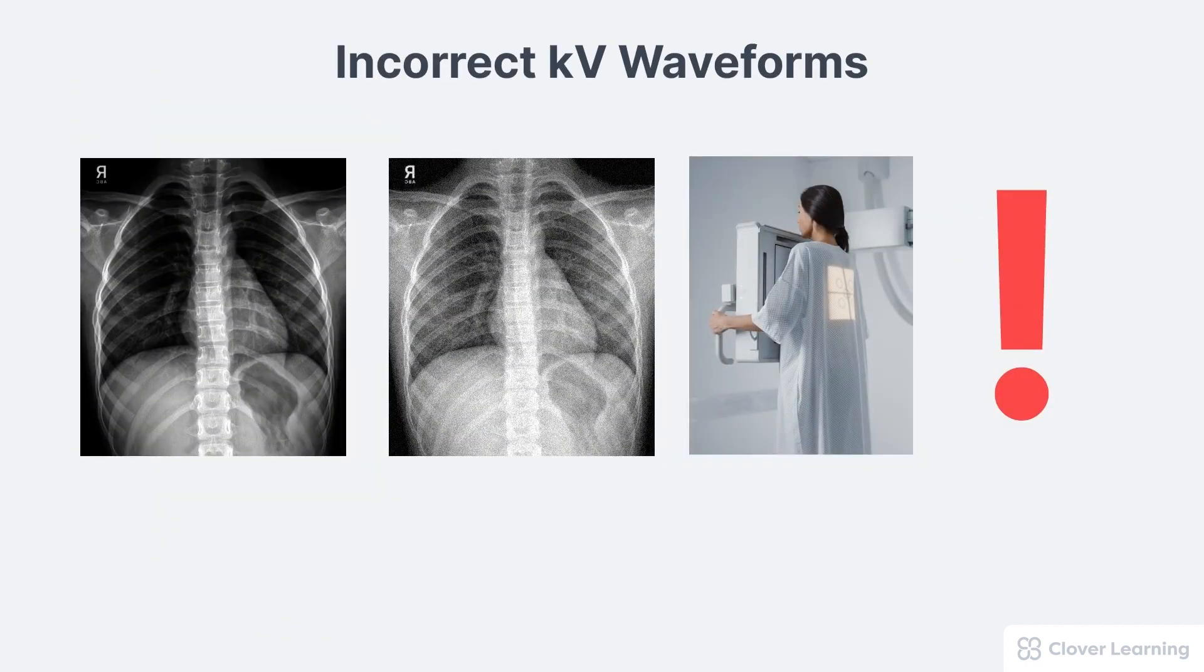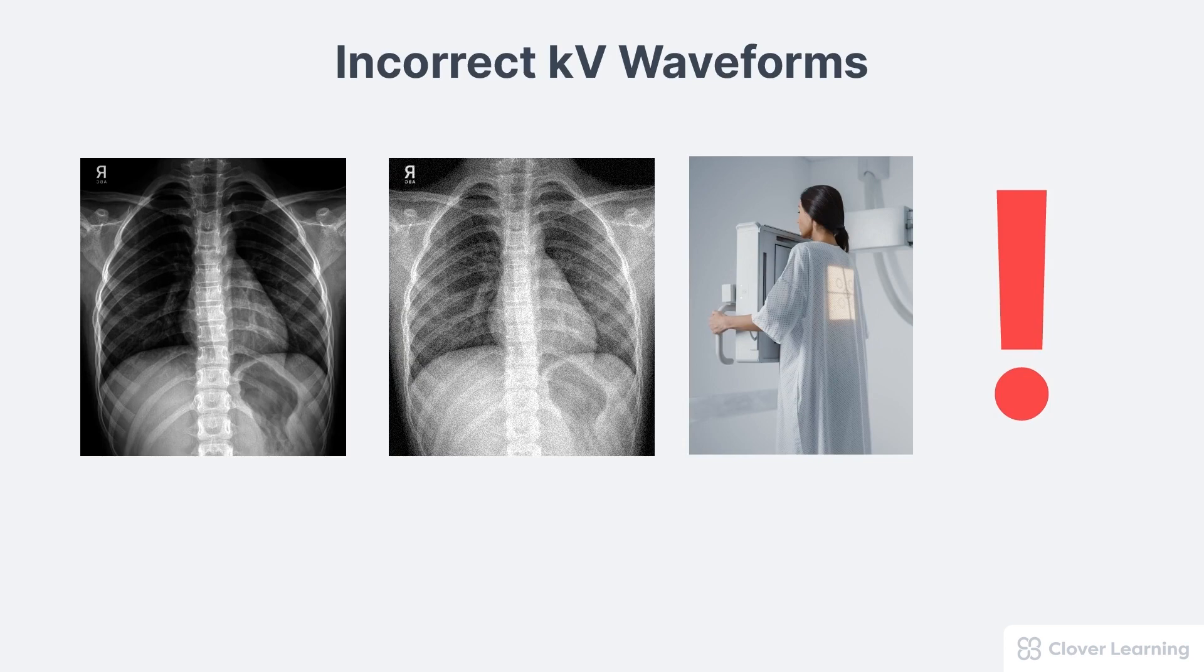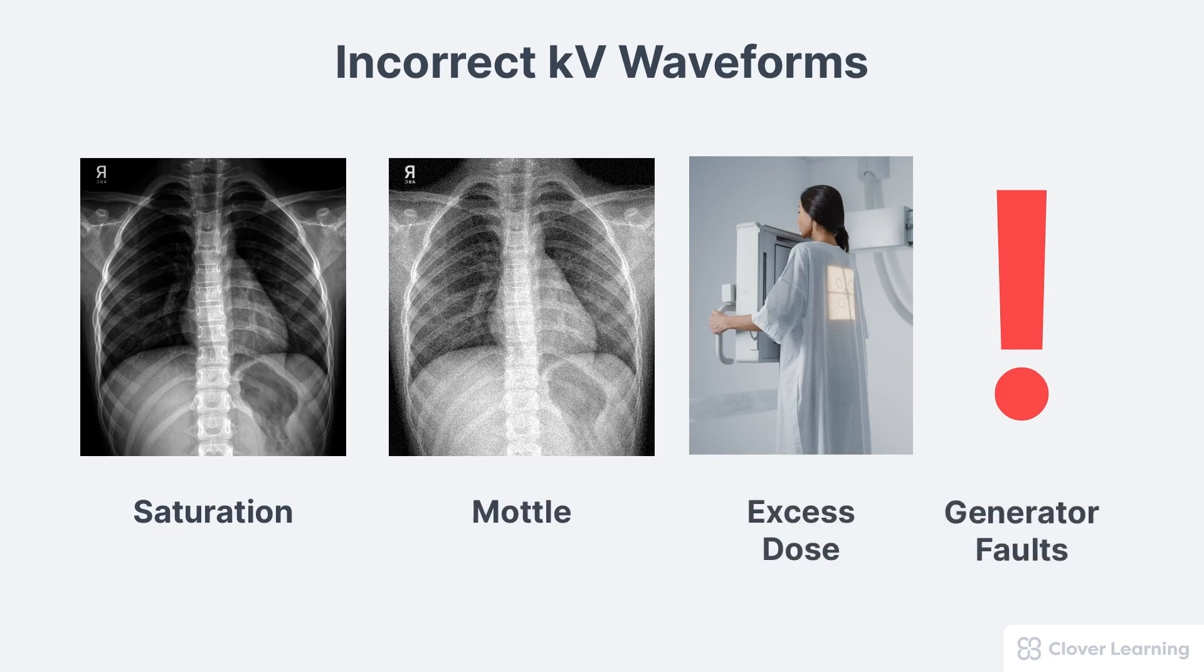Incorrect waveforms can result in several adverse effects, including various image quality issues like saturation or mottle, but also excessive patient dose and generator faults.